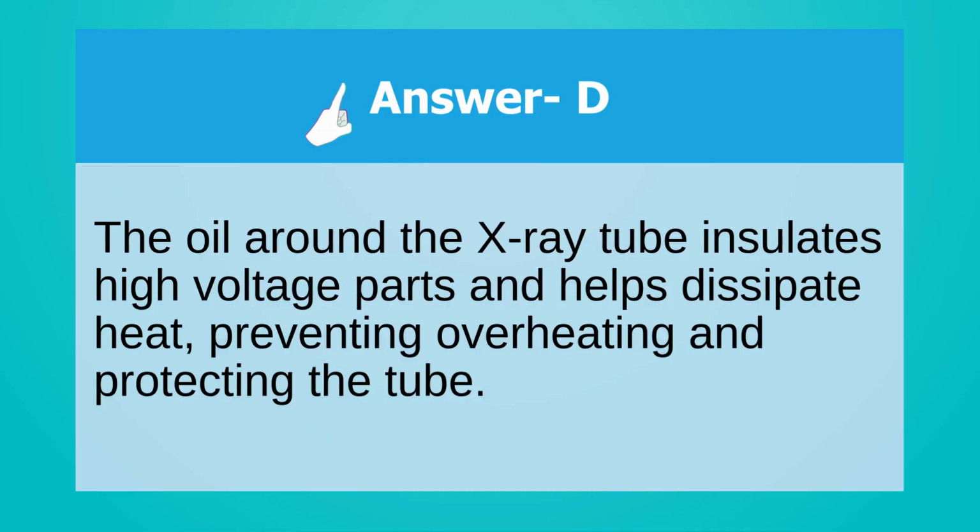The oil around the X-ray tube insulates high voltage parts and helps dissipate heat, preventing overheating and protecting the tube.